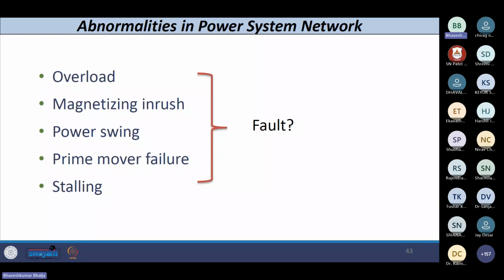However, if you have a relay or device which is going to sense the fault, then it assumes that it is a fault. So some discrimination is required to identify whether it is a fault or an inrush situation. In the same way, power swing is also there. In transmission lines, you have studied load flow studies very well, then optimized load flow or power flow, constrained optimized power flow, and so on, AC/DC power flow. So when you have the power system network at transmission level, because of the fluctuations in the power, voltage and currents are also going to fluctuate.